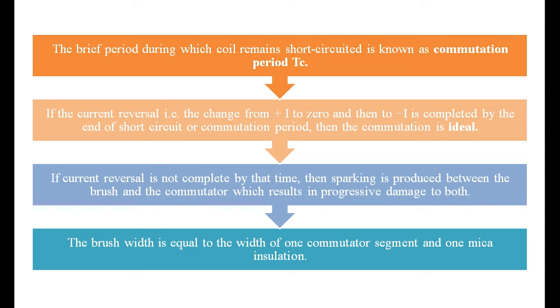If the current reversal is not complete by the time, then sparking is produced between the brush and the commutator segments, which results in progressive damage to both the commutator segments as well as the brush. Whenever there is spark progress, it will definitely affect the brush as well as the commutator segment. The brush width is equal to the width of one commutator segment - the commutator segment touching the brush is the same width. Between the commutator segments there is mica insulation that also needs to be taken care of.